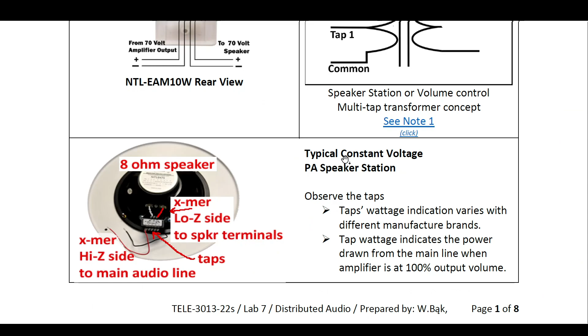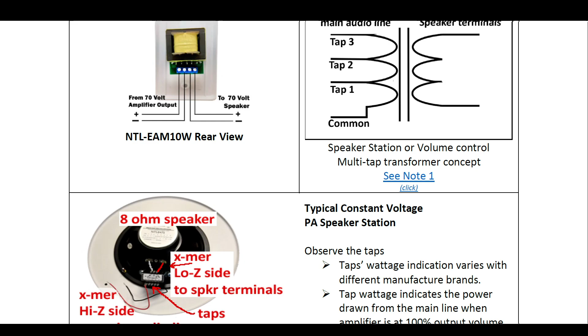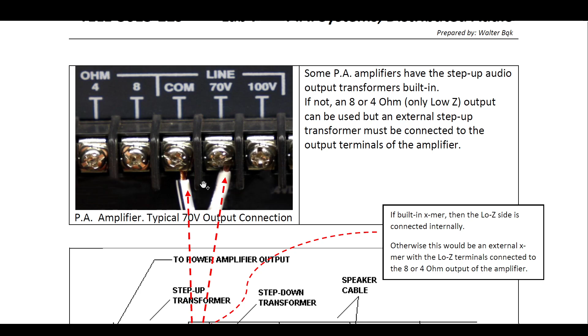Now, what does it mean if you tap the speaker at, say, 1 watt or 2 watts? This means one wire goes to common, the other goes to whatever tap represents that wattage. So if the whole system is turned to full volume, you'll have 70 volts RMS across these two terminals, and that speaker station will grab 1 watt out of the whole main line.